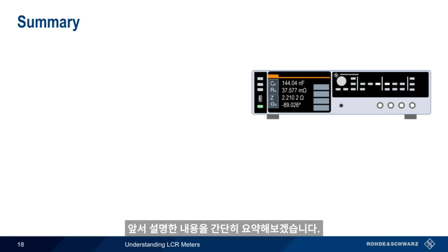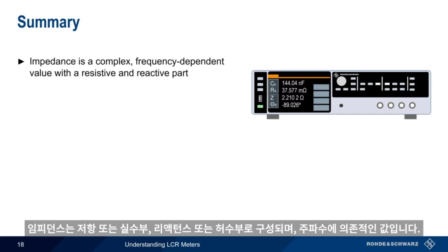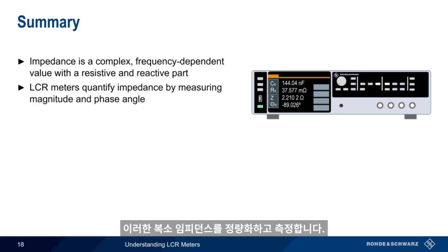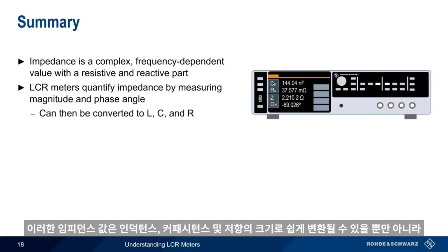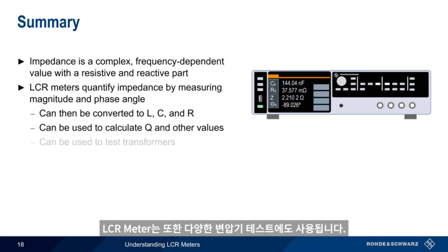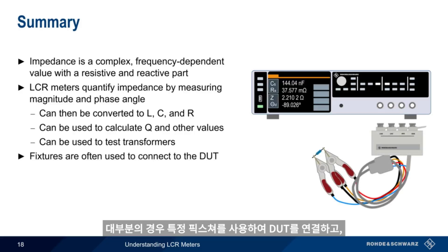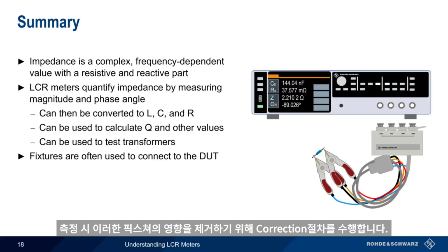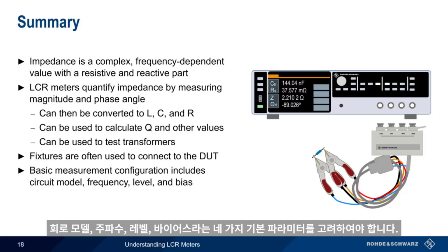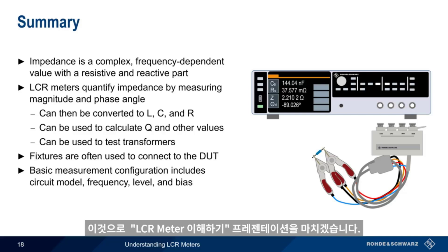In summary: impedance is a complex, frequency-dependent value consisting of a resistive or real part and/or a reactive or imaginary part. LCR meters quantify this complex impedance by measuring the magnitude of the voltage and current and the phase angle between them. These impedances can then be converted into inductance, capacitance, and resistance, as well as into other useful parameters such as the quality factor Q. LCR meters can also perform a variety of transformer tests. Special fixtures are used to connect to the device under test, and a correction or calibration routine removes the influence of the fixture from the measurement. When making measurements with an LCR meter, there are four basic configuration parameters: circuit model, frequency, level, and bias. This concludes our presentation, Understanding LCR Meters. Thanks for watching.